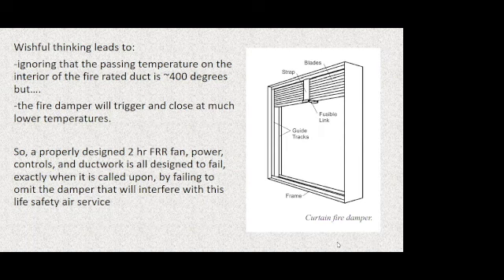the pass-fail criteria. There is no such thing as a listed damper that can be put inside of a fire-rated life safety duct that will not operate well below that threshold. So if we're looking for a duct that can survive this fire scenario, the standard time temperature, it's going to get, again, at 2 hours is a really important threshold. We're looking at around 2,000 degrees. And on the other side, the unexposed side, that's going to be around 400 degrees if the barrier is working correctly.